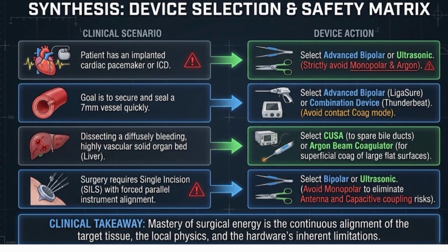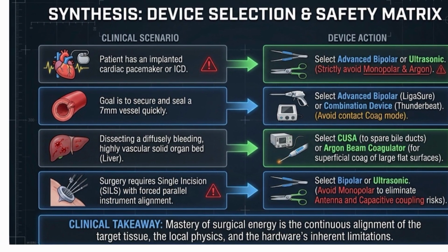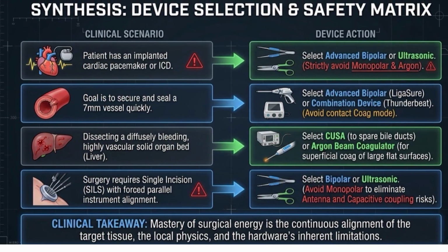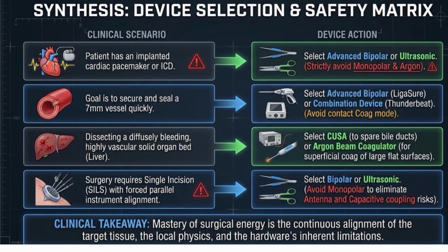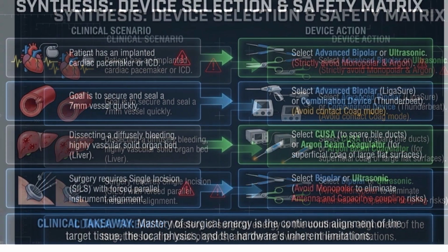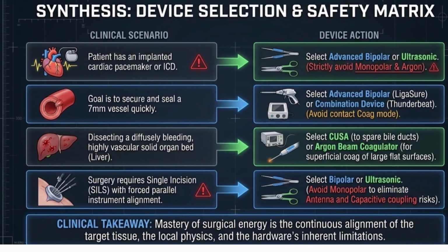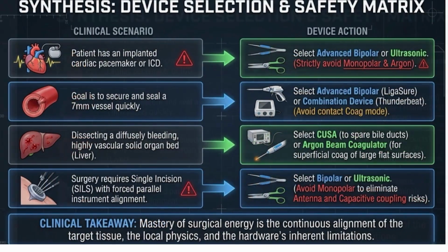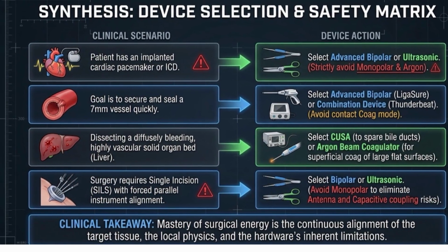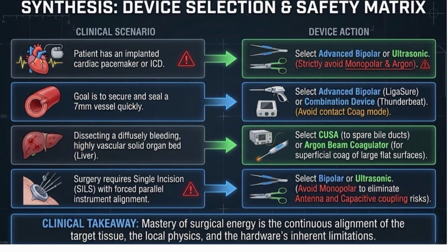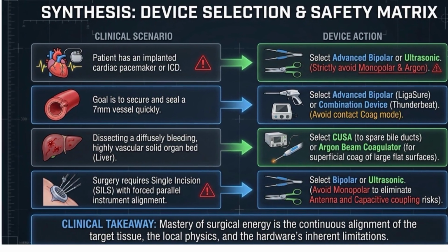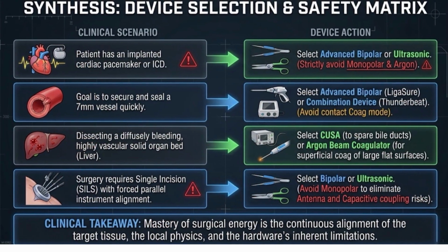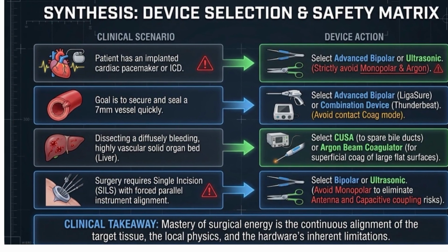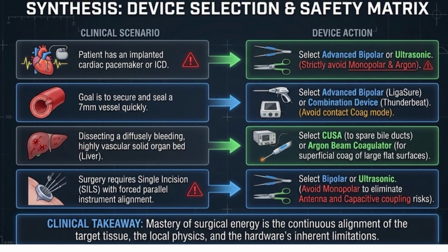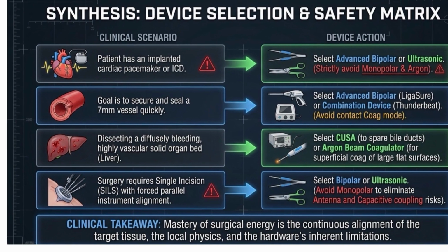In dissecting a diffuse bleeding, highly vascular solid organ bed like the liver, select CUSA to spare bile ducts, or argon beam coagulator for superficial coagulation of a large flat surface. For surgeries requiring single incision with forced parallel instrument alignment, select bipolar or ultrasonic. Avoid monopolar to eliminate antenna and capacitive coupling risks. Mastery is continuous alignment to the target tissue, the local physics, and the hardware's inherent limitations.